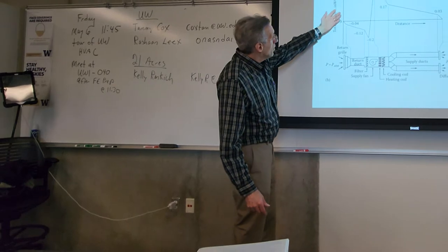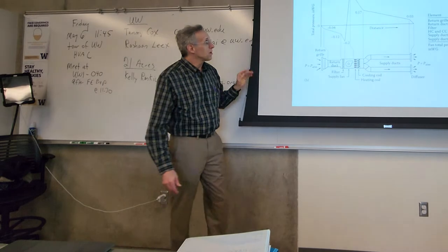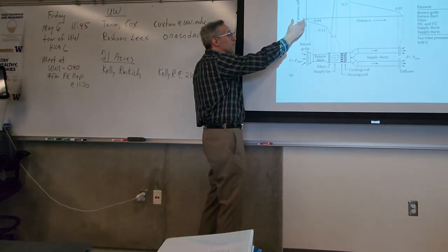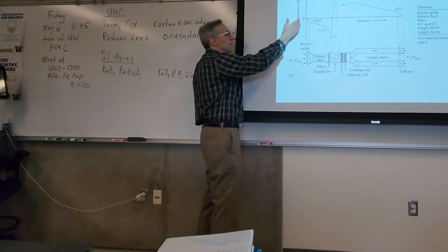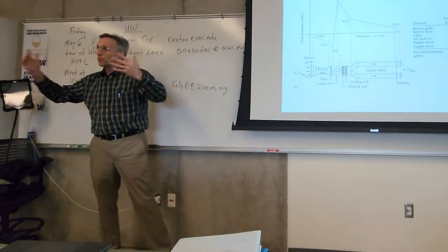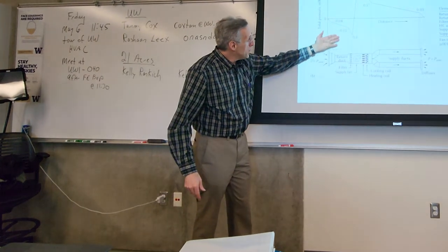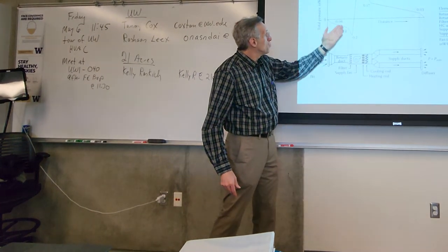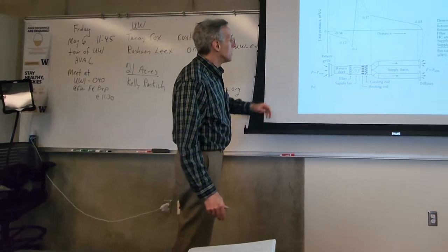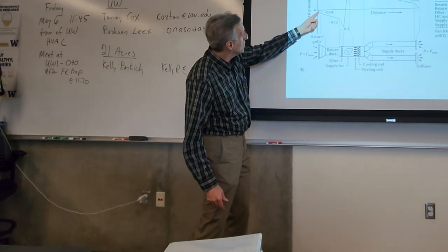And this is nice because it shows the pressure changes as you work your way through the system, starting with just regular room atmospheric pressure. Now this is gauge pressure here. So gauge pressure means that it zeroes out at atmospheric pressure, whatever the pressure in the room is. That's zero, and then the measured pressures in the system are measured relative to the pressure in the space and the surrounding air.